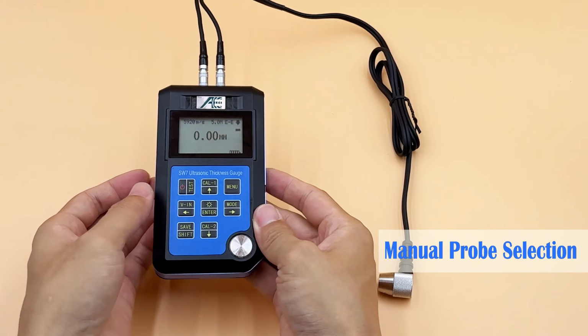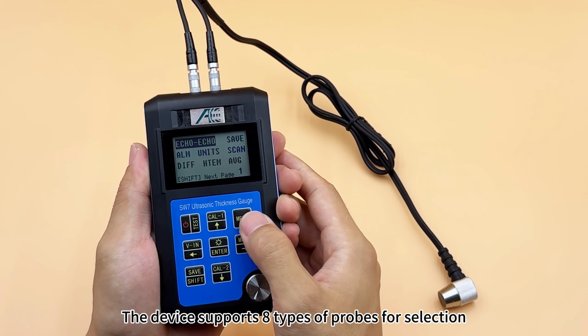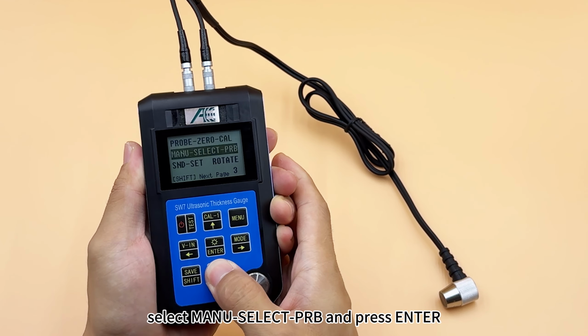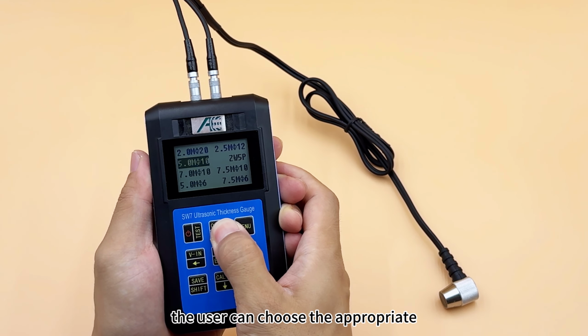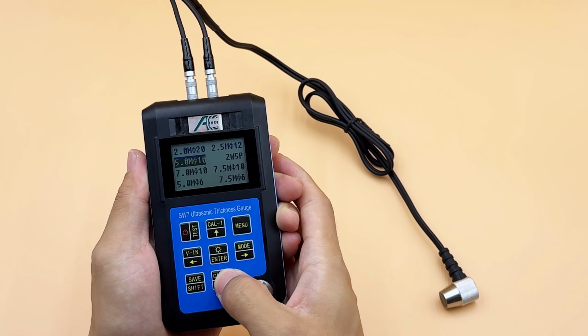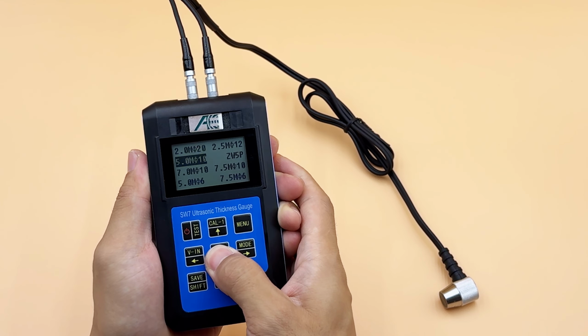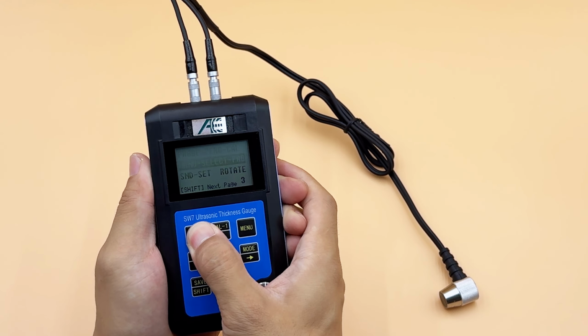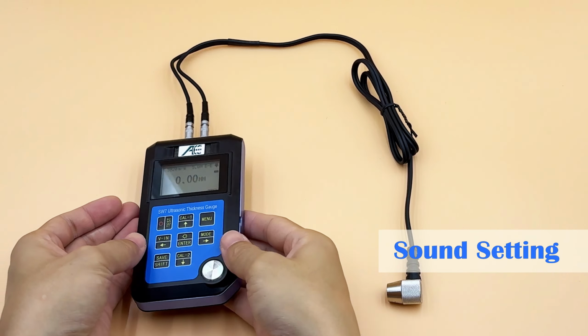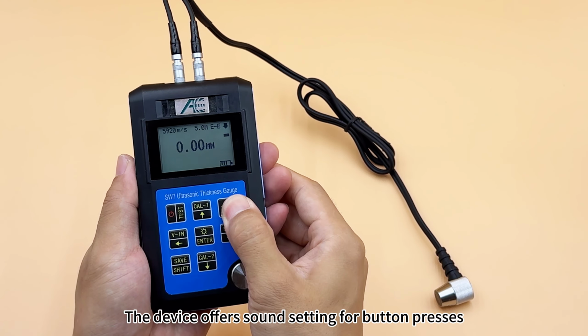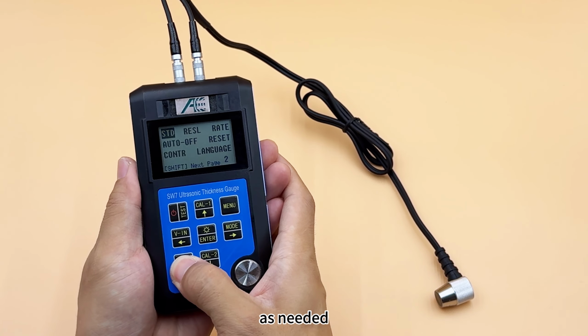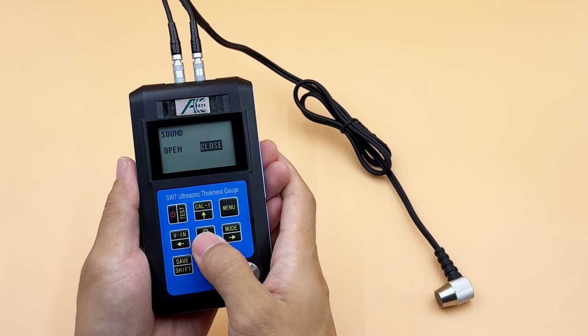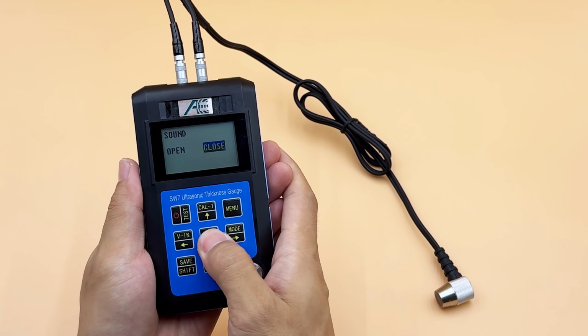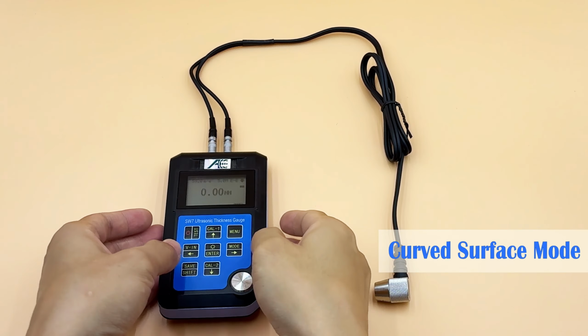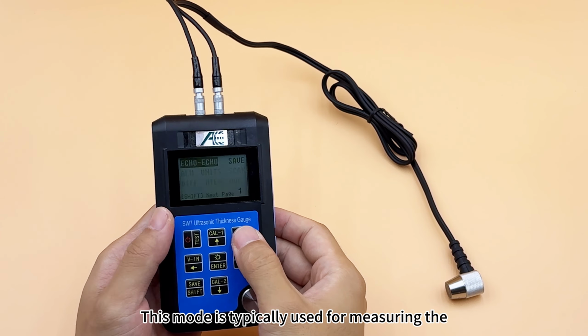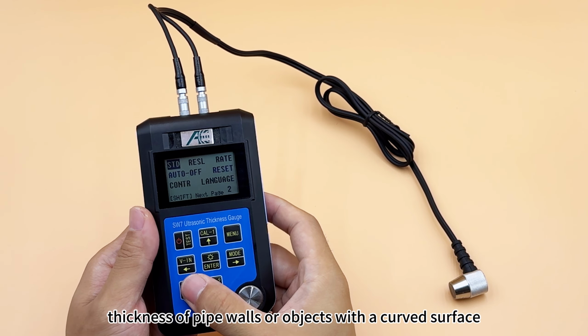Manual probe selection. The device supports 8 types of probes for selection. Press Menu button, select Manu Select Probe, and press Enter. The user can choose the appropriate probe according to connected probe. Sound setting. The device offers sound setting for button presses, allowing users to enable or disable the button sound as needed. Curved surface mode. This mode is typically used for measuring the thickness of pipe walls or objects with a curved surface.